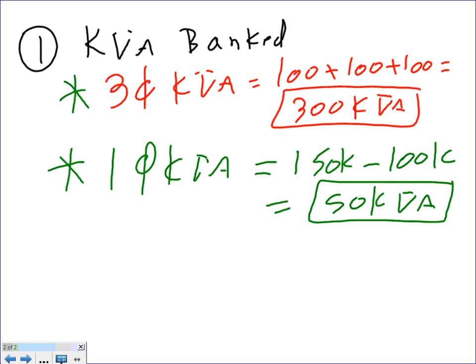So what does that mean, guys? When you add all your three-phase equipment, keep adding. When you hit the 300, you stop, three-phase. Then you go to the single-phase equipment. You add your single-phase equipment. When you hit the 50, you stop.